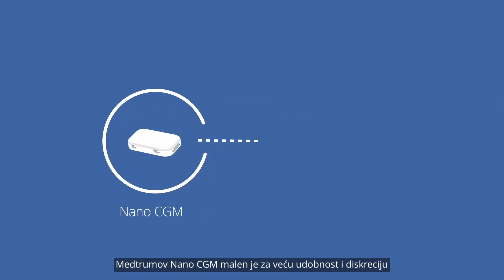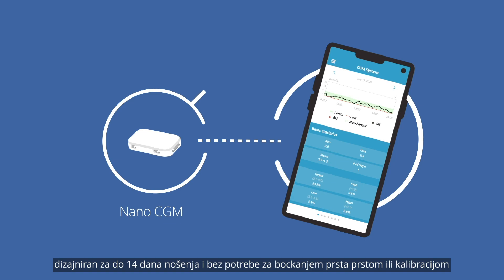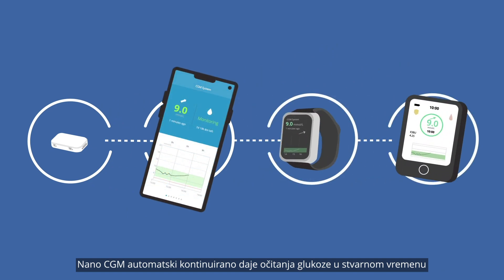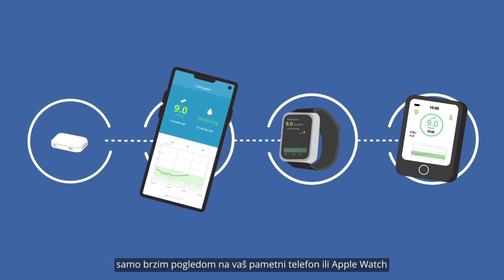Medtrum's Nano CGM is tiny for improved comfort and discretion. Designed for up to 14 days wear with no finger pricks or calibrations, the Nano CGM automatically provides real-time glucose readings continuously, letting you know your current glucose levels, which direction it's heading and how fast it's changing.